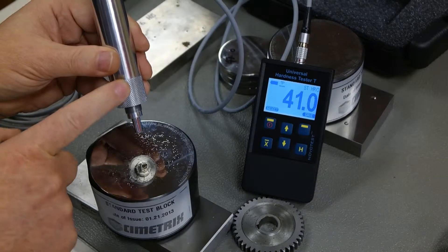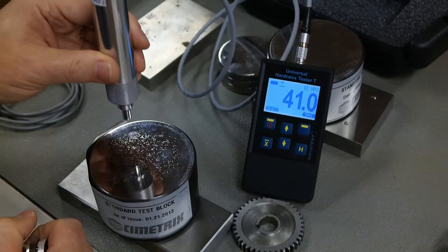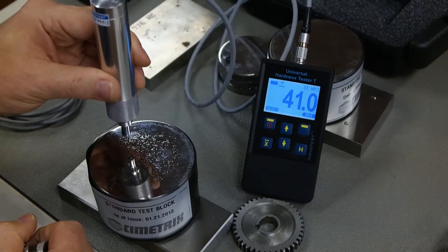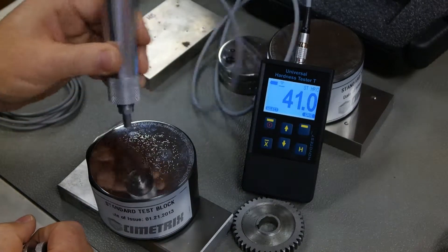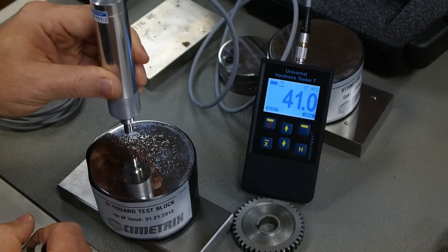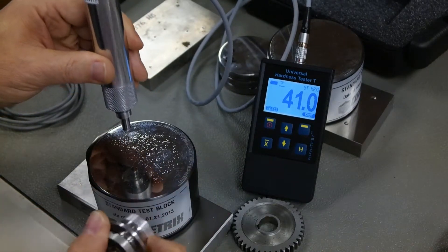In this case, this is a 50N, so it's about twelve and a half pounds of load. But as soon as the tester senses that, it recognizes that you can't move the probe around. It's got to stay very steady, otherwise you'll get erratic readings.